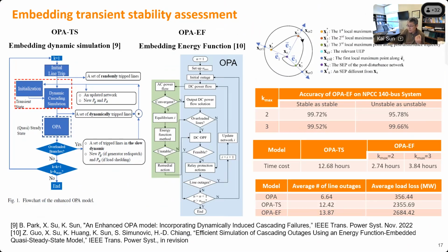Then you can compare different OPA models. The first OPA model is just the original model without transient stability. The model tells you the average number of line outages will be 6 to 7, and the average load loss will be more than 300 megawatts. But if you consider transient stability, using the time domain simulation or the energy function, they give very similar results, and you see they are much more severe than the OPA-only model, which means you do need to consider transient stability to make your simulation more accurate, either using the time domain simulation or the energy function.